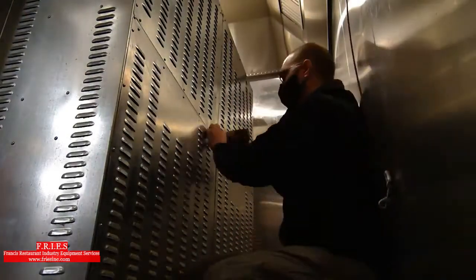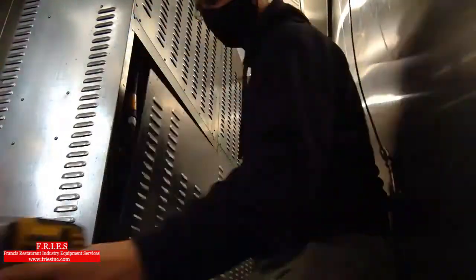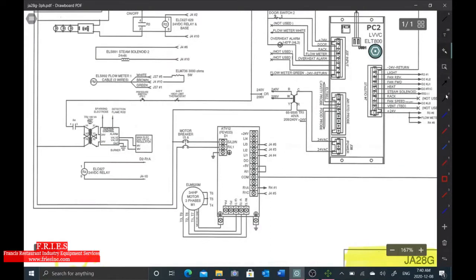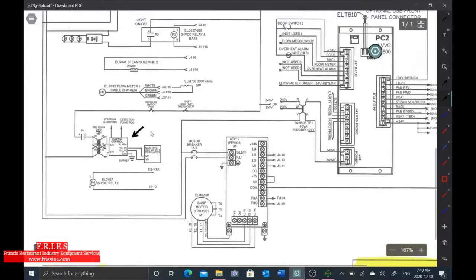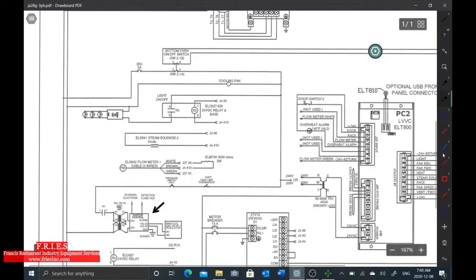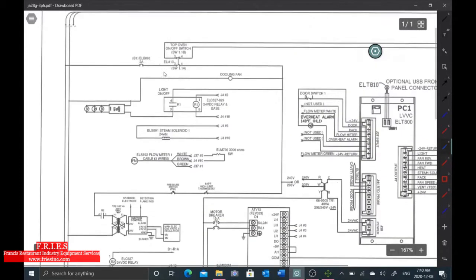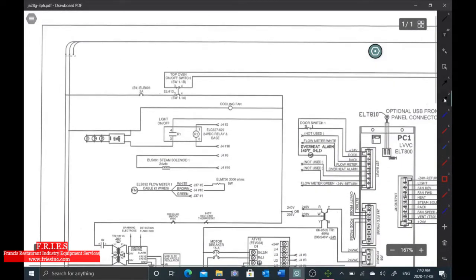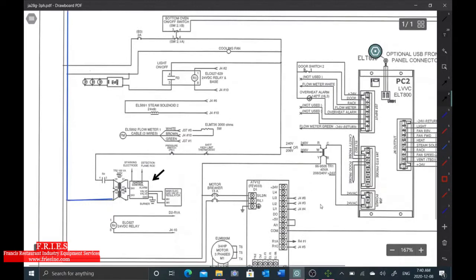Okay, I'm going to rip this back panel off. Okay, and it's going to expose all the components I need to test, and I'm going to go through the sequence of operations. Alright, so my goal is to get to this ignition module here. So I'm just going to map out the sequence really quickly. So if we follow here, we have our transformer. Okay, our transformer is being fed all the way up here to our incoming power. So it does go all the way up. I'm not going to draw it, but the incoming power is all the way here. That's your L2. Okay. And then the second side of the circuit, which is my L1 side, is coming through here.